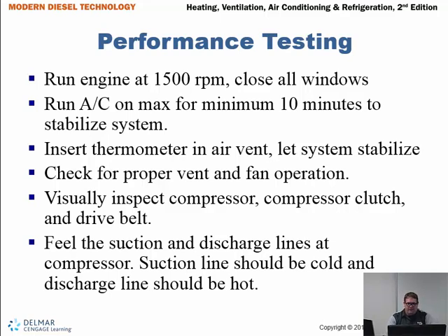Insert a thermometer in the air vent, and sometimes that air vent, they want it in the closest air vent to the evaporator. They'll tell you to close the other air vents. So again, follow the manufacturer's instructions to the best of your ability. Let the system stabilize.